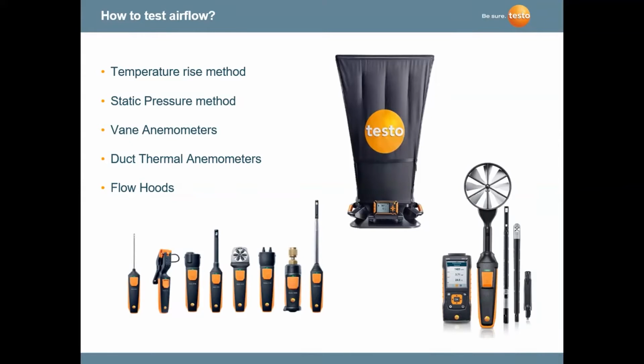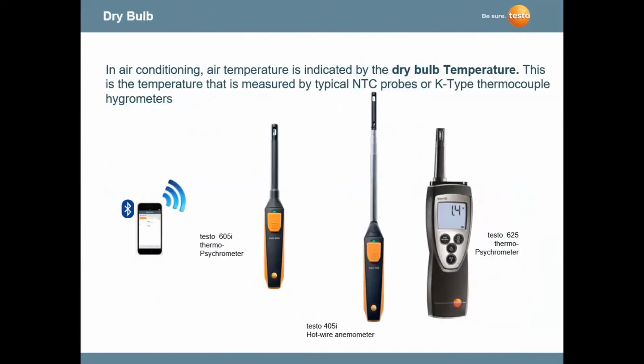One thing to know is when we're doing an airflow test, typically we're measuring the feet per minute, and feet per minute is the speed or the velocity of air. We still need to look at the area of the duct size to get the cubic feet per minute, or CFM. And that's a volume measurement. CFM is a volume measurement. So we need to know the dimensions of the duct itself so that we can get the correct area, and we can calculate the CFM from the feet per minute that we're measuring.